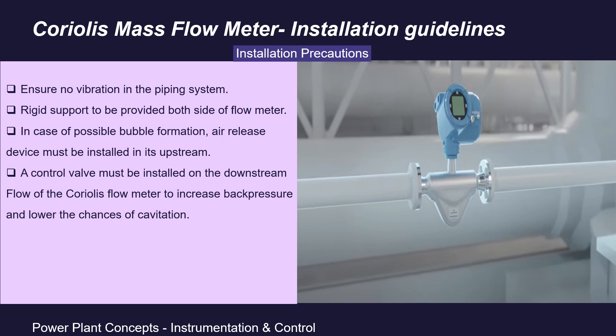There are some points to take care of during installation. First, as Coriolis flow meters are highly sensitive to vibrations, any external vibrations can cause errors in measurement — so the pipeline where it is installed must be free from vibrations. Second, both sides of the flow meter must be supported rigidly. Also, if there is any chance of bubble formation in the fluid, an air release device must be installed upstream. A control valve must also be installed on the downstream side to increase back pressure and lower the chances of cavitation.